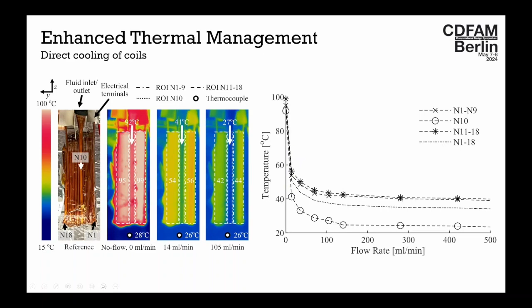An alternative is to look at using end-winding heat exchangers. The active length of a machine, where those channels would be, is actually a really valuable part of the machine and ideally would be taken up by conductive material. So if we can come up with schemes where we don't have to take the active length region and can just work at the end winding, then we will take that option.